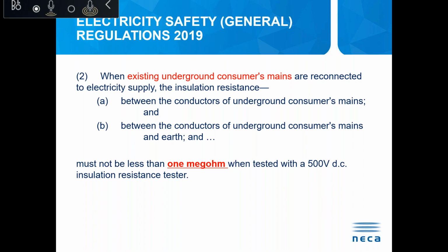If you are doing an existing repair, then you can rely back on the old requirement of 1 meg ohm when tested at 500 volts DC with an insulation resistance tester.